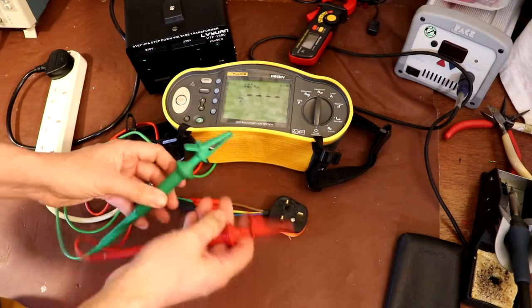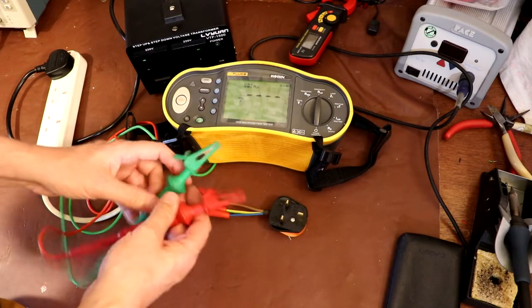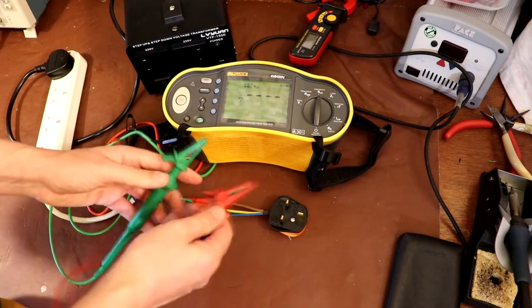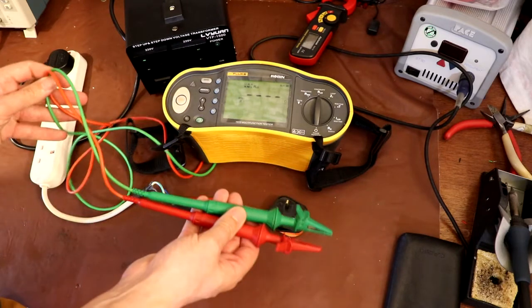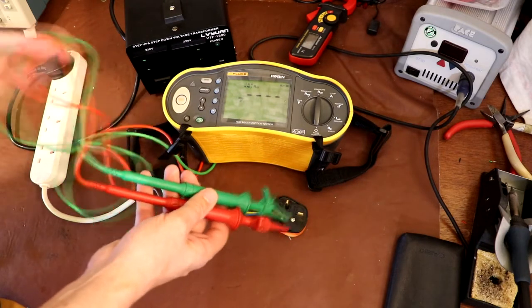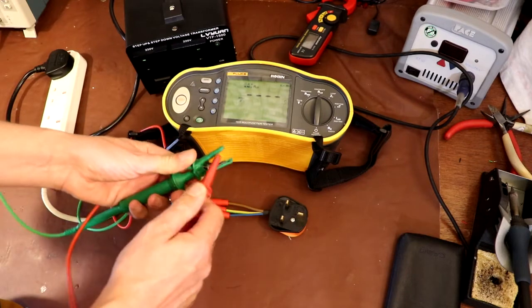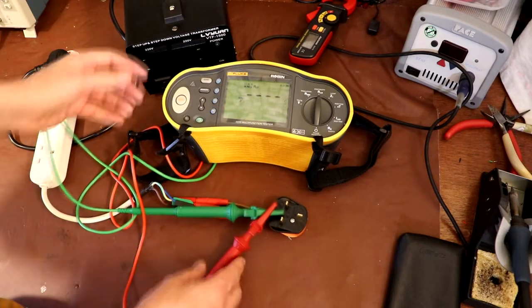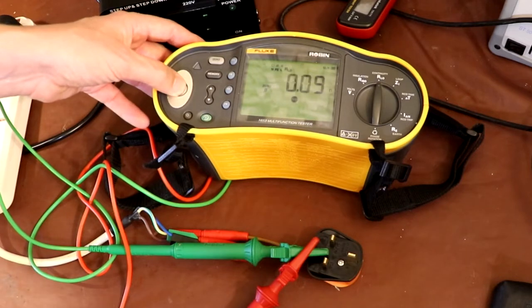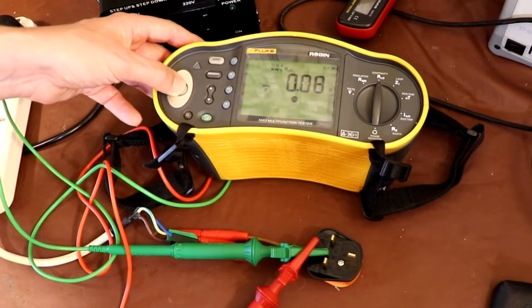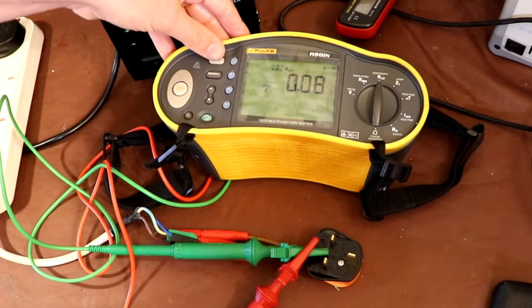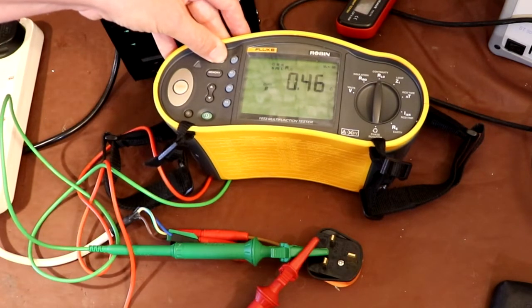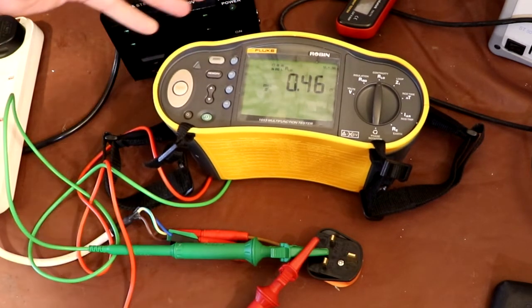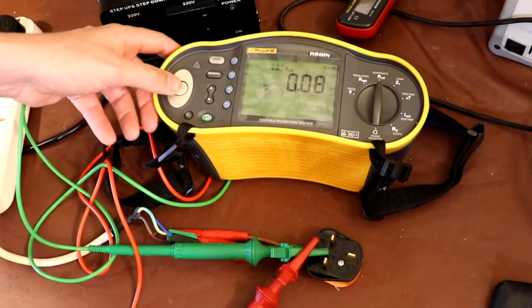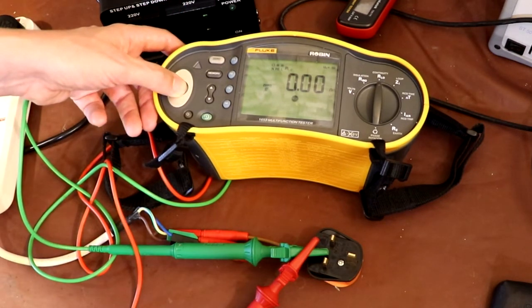Now before we take the resistance of our transformer, it's going to be a very, very low reading, so we don't want the resistance of the test leads to interfere with the measurement we get. So we've got to null them out. So we clip them together, and I think we press test on this meter, and I think I release that button, and I think I hold it down, and it zeroes out. And I think if I press test again, okay, so that's coming up 0, 0, 0.